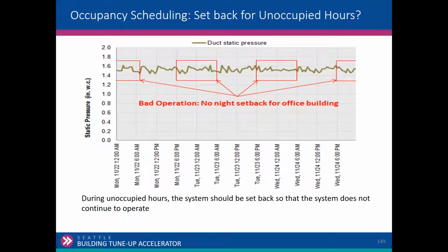Here's a situation where there was no setback. So during unoccupied hours, this should set back, so it was just maintaining. This was duct static pressure. So if your fan is running 24/7, the static pressure is going to be fairly constant here. So we can verify through duct pressure, we can verify through space temperature, we can verify through fan operation, motor start, stop. So there's a couple of different ways of verifying scheduling.